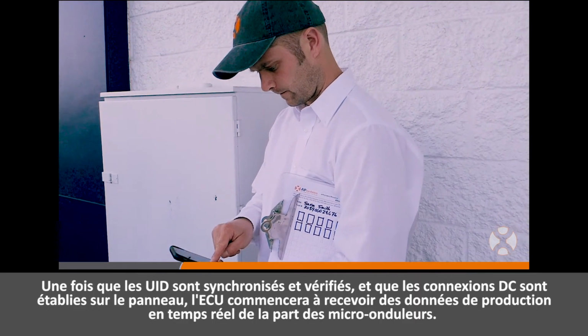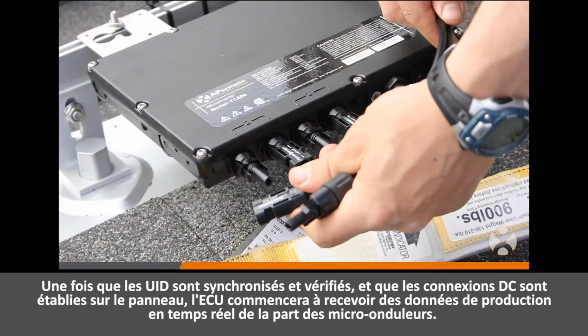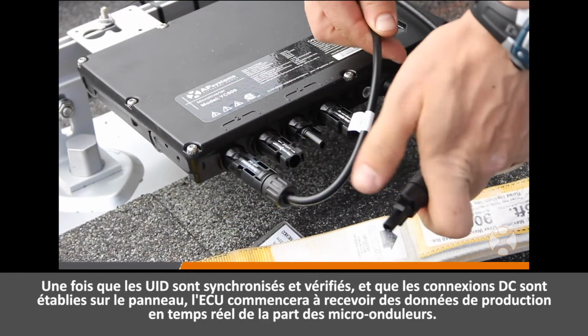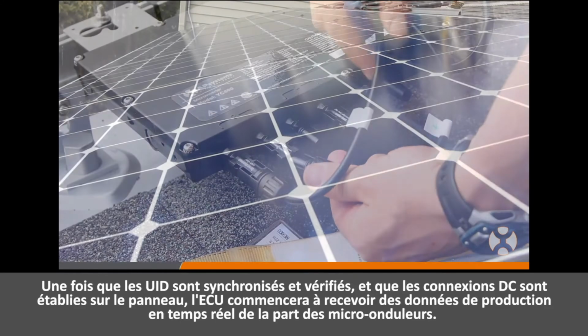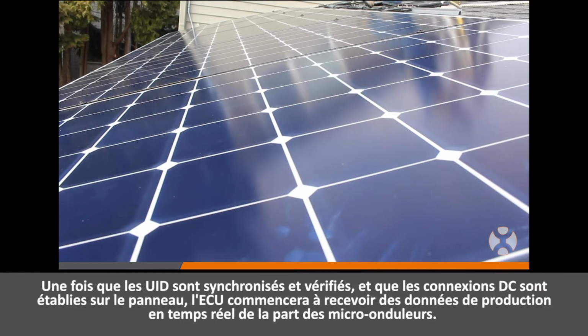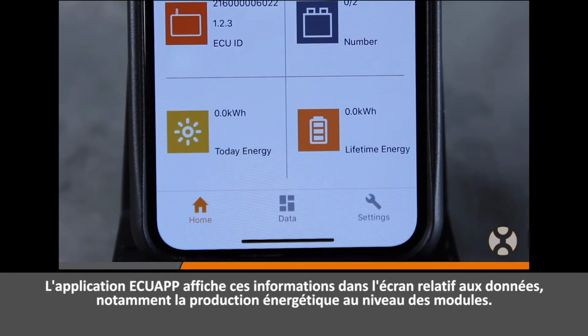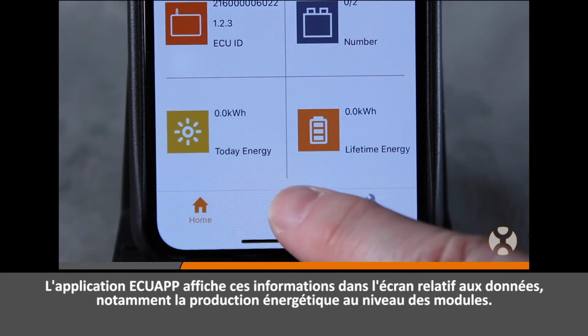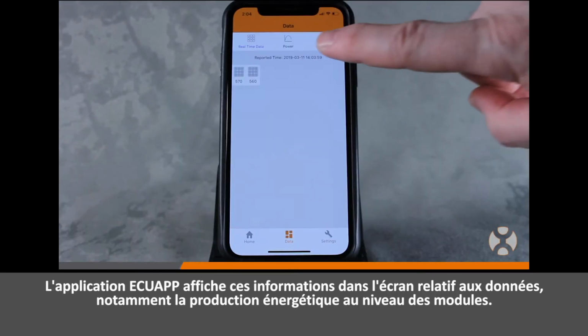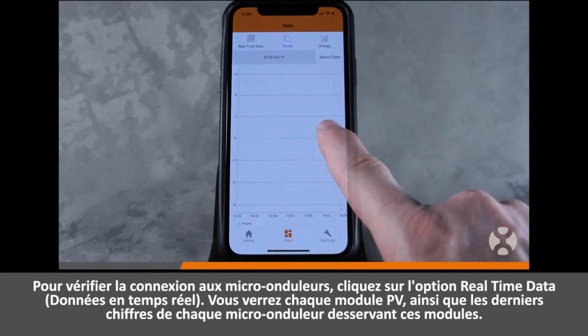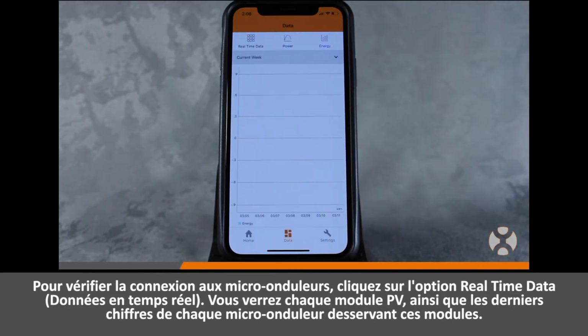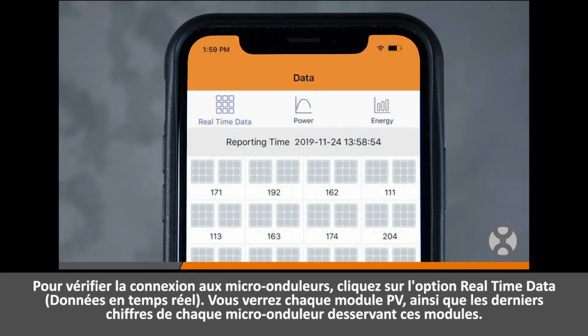Once the UIDs are synced and verified, and the DC connections on the array are made, the ECU will begin receiving real-time production data from the inverters. The ECU app displays this information on the data screen, including module-level power production. To verify connection to the microinverters, click on the Real-Time Data option, and you'll see each PV module as well as the last few digits of each microinverter serving those modules.